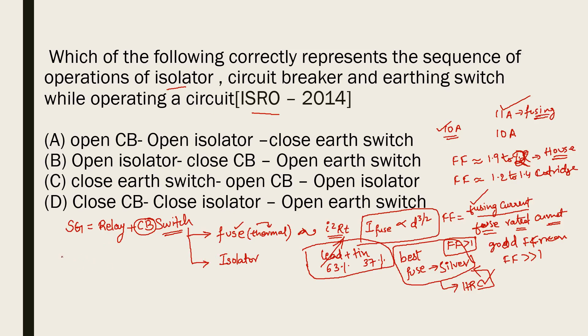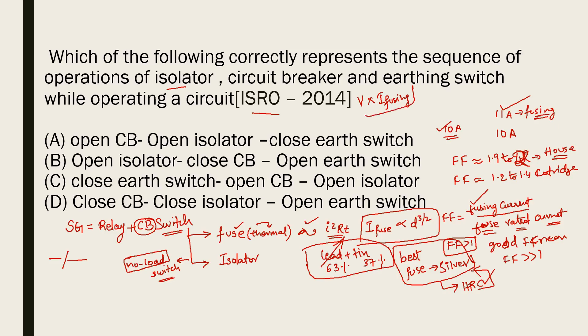Next, the isolator: its circuit symbol is distinct. An isolator is also called a no-load switch because it is operated only under no-load conditions — there should be no current during its operation. Regarding ratings, the rating of a fuse is system voltage × fusing current. More generally, the rating of any switch equals system voltage × switching current, where switching current is the current flowing through the switch at the time of making or breaking.